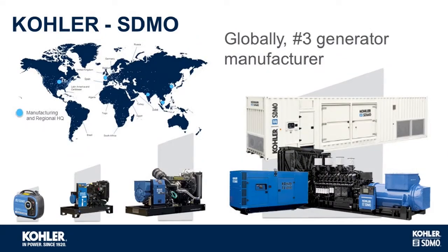We are the third largest generator OEM in the world. We manufacture generator sets from just a few kilowatts, which is the small unit on the left-hand side, right up to the largest data center designed high-speed generator set in the world, rated at 4,000 kilowatts or 4,500 kVA, which is produced in our factory in northern France, where we also package them in-house into a range of enclosures, from the simple dropovers, which is the blue unit in the centre of your screen, to the larger ISO-style containers, which are typically 12 metres long and would meet noise levels of around 80 to 85 dBA, right through to bespoke walk-in enclosures, which are capable of achieving very low noise levels within the smallest of footprints, therefore best suited to hyperscale data centres.